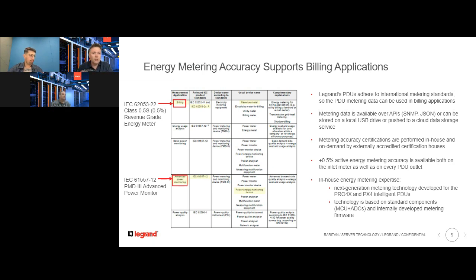So the good news from us is you can rely on the accuracy of the energy metering data provided by our PDUs. We do qualify and certify our energy metering circuitry in-house and also on demand by externally accredited certification houses. The third-party DCM software, like Calvin mentioned already earlier, is usually used to collect the energy metering data over longer time periods to create monthly or annual energy spending reports. And a good advantage of the new generation architecture is we have implemented the firmware of our metering chips in-house. And that's why we are not locked into a specific chip vendor anymore. And this allows us to mitigate supply risks in the future.